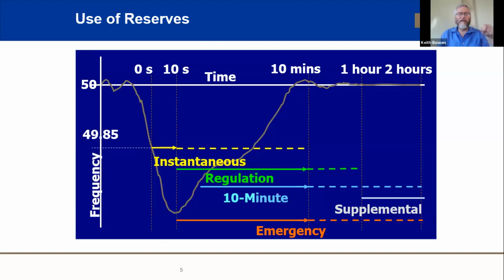That primary reserve that David mentioned, which is this instantaneous reserve, is when things go outside that window. Normally it triggers at about 49.7 on the downside. If you pick up that you've dropped below that, as David did mention, there's a relay at each of the power stations, and it can be at a large number of customers, particularly big smelters, where they can actually interrupt. So the customers see the relay, it triggers a response. It doesn't have to be indicated by a central system. They just see the relay. They know I have to respond to this event. And so therefore they withdraw demand, maybe for 10 seconds.